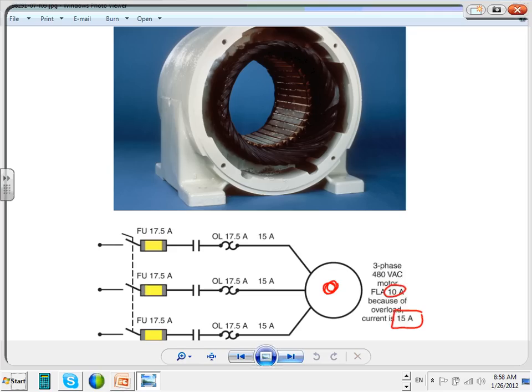I have 15, 15, 15 amps going through my motor, but my overload is sized at 17.5. Do you think it's going to trip? The overload is going to trip? No, it's not going to trip. Look at the current that I'm taking, it is 15 amps. The overload is sized for 17 and a half, and this one is sized for 20 amp. Do you think the 20 amp is going to trip first? That's full load. No. Do you think the 17 and a half? This is as high as you can get, 17 and a half, and I'm still at 15. Do you think this is going to trip? No. So this motor is going to be pulling 15 amps continuously until it burns itself.